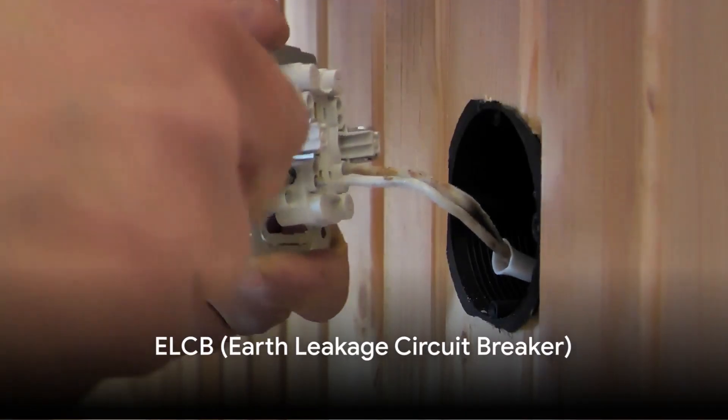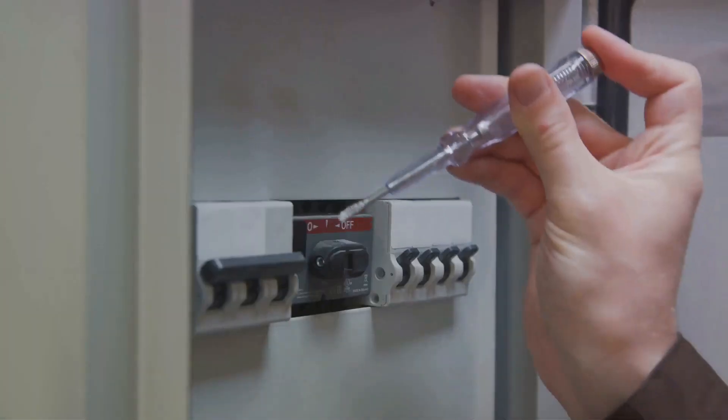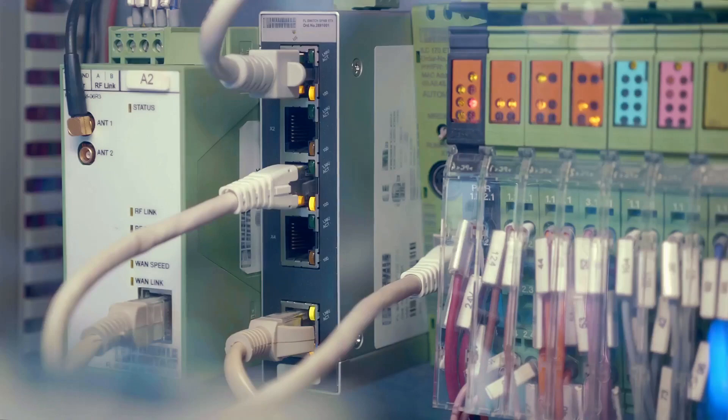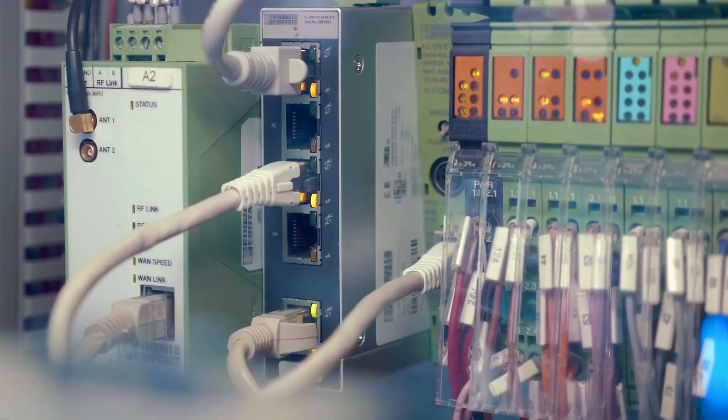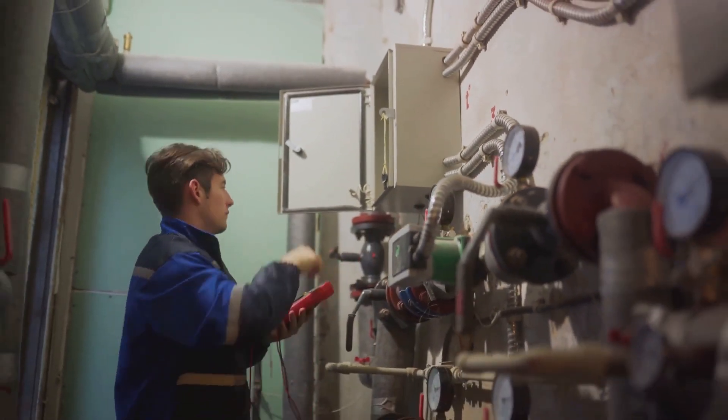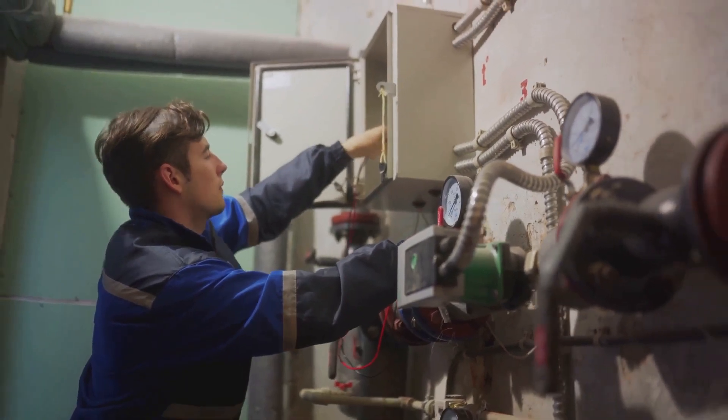Next, we have the ELCB or Earth Leakage Circuit Breaker. Much like the RCCB, the ELCB is designed to protect against electric shock. However, its operation is slightly different. The ELCB works by comparing the current flowing in the live wire with the current returning through the earth wire. If it detects an imbalance, it trips, cutting off the power supply. ELCBs are commonly found in older electrical installations.